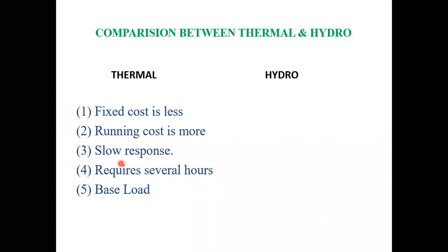And similarly, it is a slow response. Why does it give a slow response? When you are considering a thermal power plant, so many units are there, especially boilers, superheaters, and turbines. When you use these boilers and superheaters, this unit will take a lot of time. It takes several hours to take the load. So that's why we can say it is a slow response.